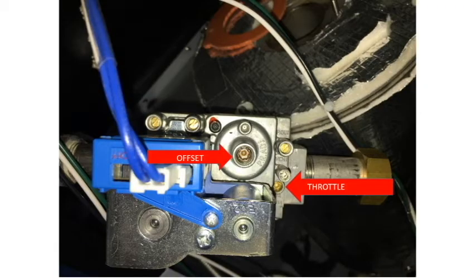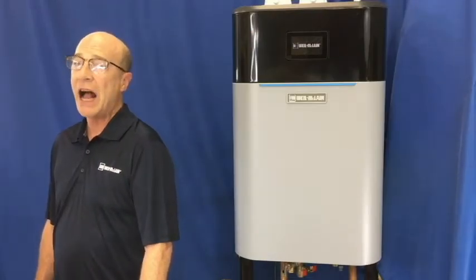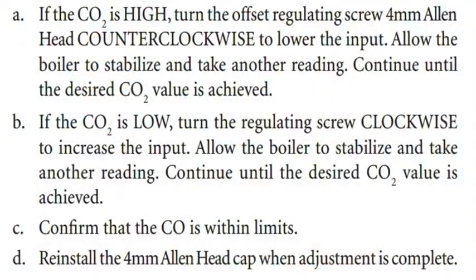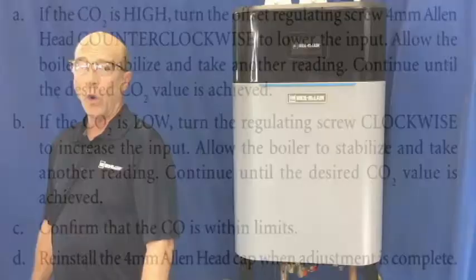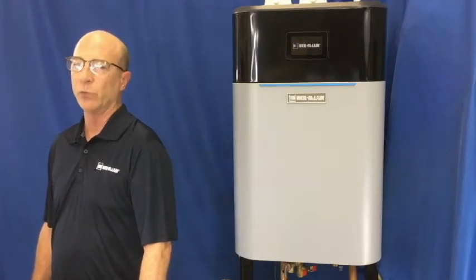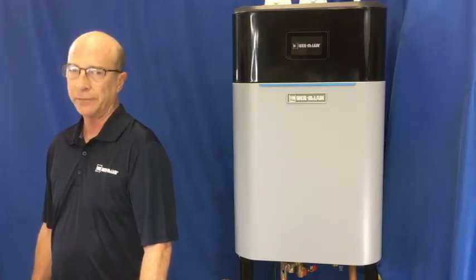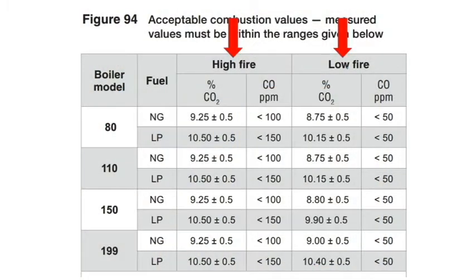Now, let's look at the low fire readings. Check your CO2 level. If it's high, turn the offset screw counter-clockwise. If low, clockwise. Once you have hit the target, observe the carbon monoxide reading and compare it to the chart.